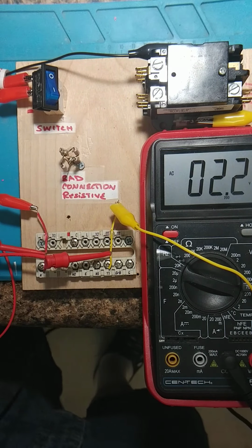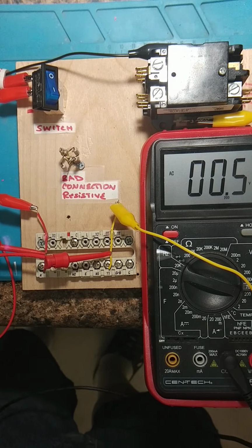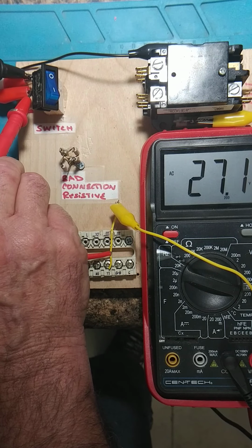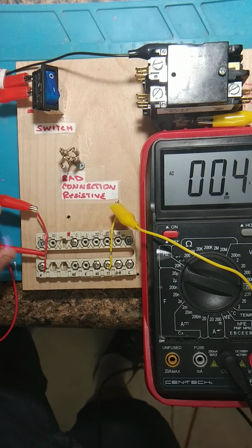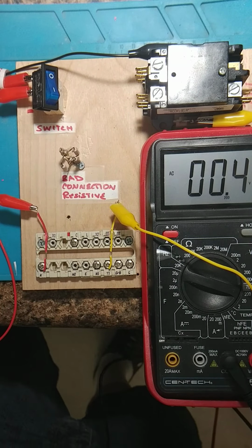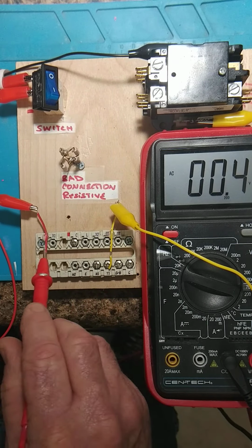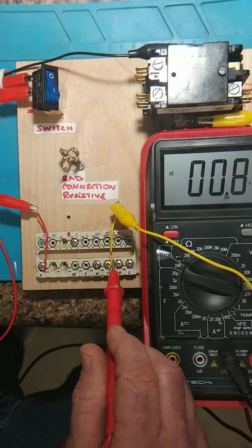So if your thermostat is calling for cooling, and you're trying to trace out where your open is, if you check across your float switch, you should have your low voltage. Now, if I have a thermostat off the sub base, I no longer have that connection at the thermostat. So common is going to stop right here.